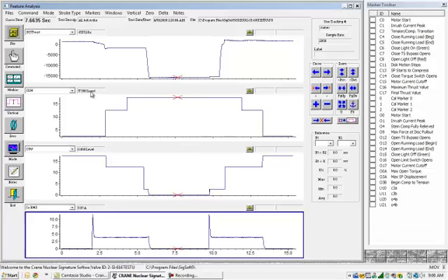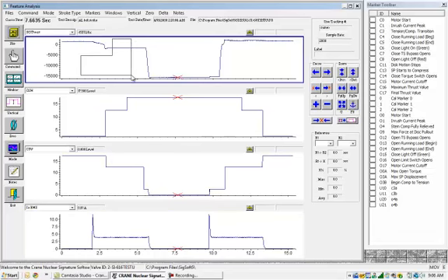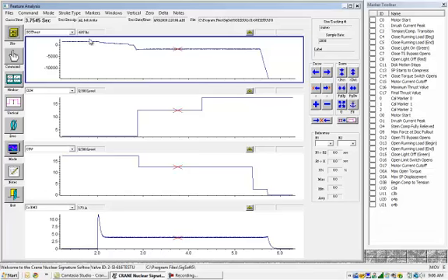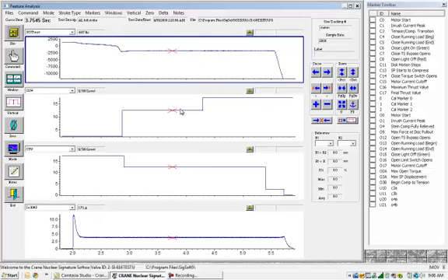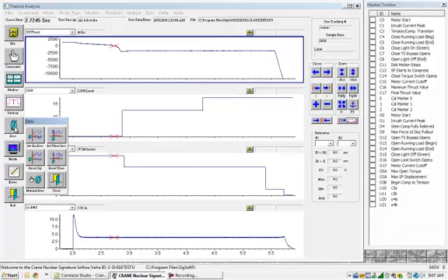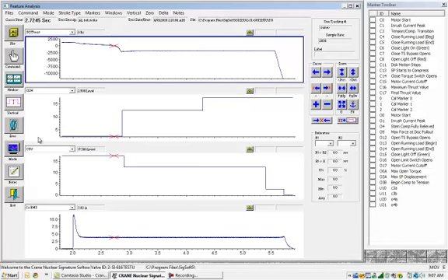Alright, so the first thing I'm going to do, I'm going to look at this trace here, zoom in on this. We know that the motor start is here, so the first thing that's going to happen is the tension of the stem is going to go away and level off at some point. So right now I'm going to pick this point just for argument's sake. To set the 0, you're just going to put 0, set sig 0, that does it, and at that same point I'm going to mark C3 because it's our tension to compression region.